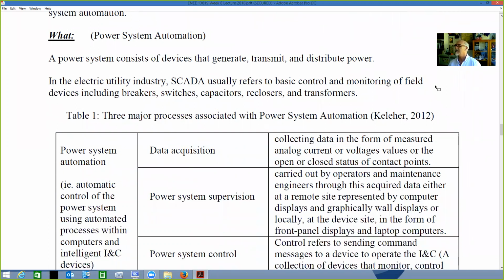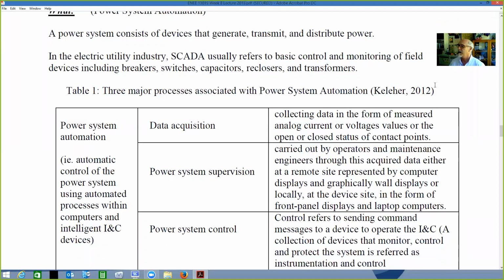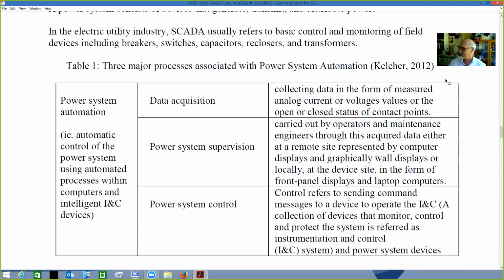A power system consists of devices that generate, transmit, and distribute electricity. In the electric utility industry, SCADA usually refers to basic control and monitoring of field devices, including breakers, switches, capacitors, reclosers, and transformers. Data acquisition occurs, collecting data such as measured analog current or voltage values, and open or closed status of contact points. Power system supervision is carried out by operators and maintenance engineers through acquired data from substations, generators, pumps, and a whole range of things.